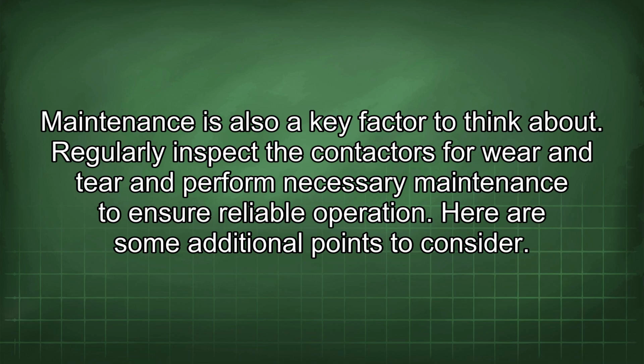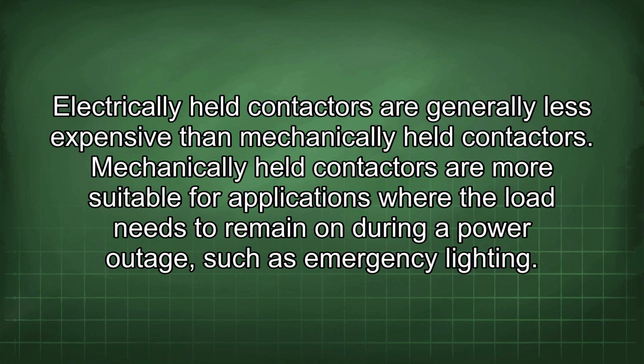Maintenance is also a key factor to think about. Regularly inspect the contactors for wear and tear and perform necessary maintenance to ensure reliable operation. Here are some additional points to consider. Electrically held contactors are generally less expensive than mechanically held contactors.